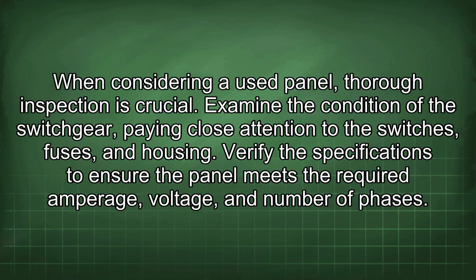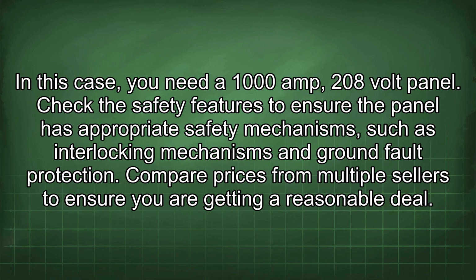When considering a used panel, thorough inspection is crucial. Examine the condition of the switchgear, paying close attention to the switches, fuses, and housing. Verify the specifications to ensure the panel meets the required amperage, voltage, and number of phases. In this case, you need a 1000 amp, 208 volt panel.